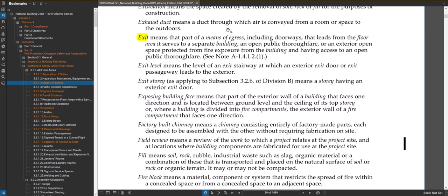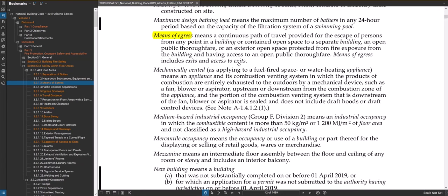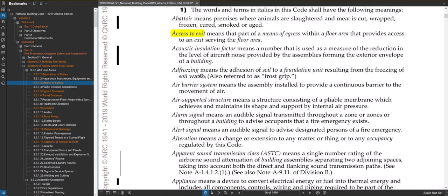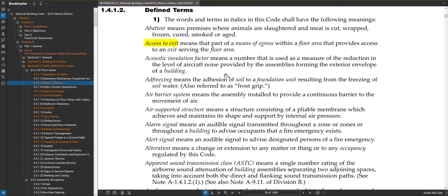We commonly refer to stairs in multi-story buildings as exit stairs. There are two types: a convenience stair, which isn't a protected zone, and exit stairs, which are protected zones on the path of your means of egress to the exterior. The final definition to look at is access to exit — that part of a means of egress within a floor area that provides access to an exit. A corridor, for example, gets you to the exit stair and would be considered an access to exit.